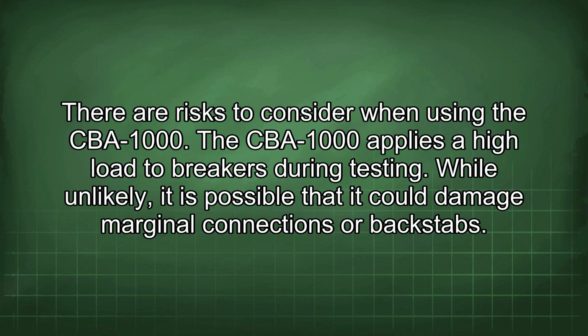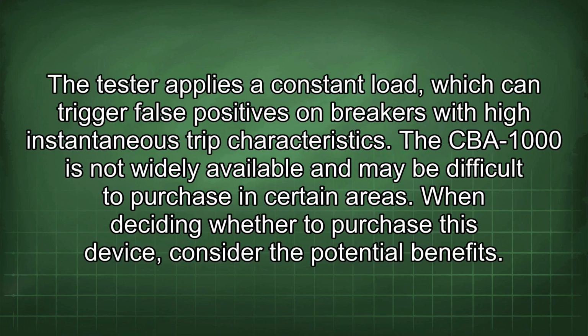There are risks to consider when using the CBA-1000. The CBA-1000 applies a high load to breakers during testing. While unlikely, it is possible that it could damage marginal connections or backstabs. The tester applies a constant load, which can trigger false positives on breakers with high instantaneous trip characteristics. The CBA-1000 is not widely available and may be difficult to purchase in certain areas.